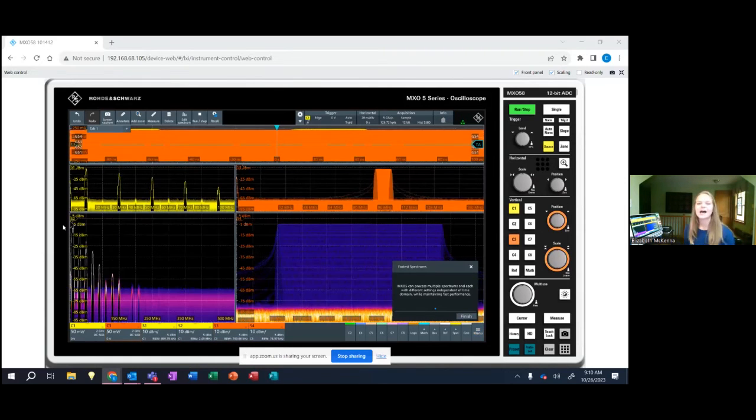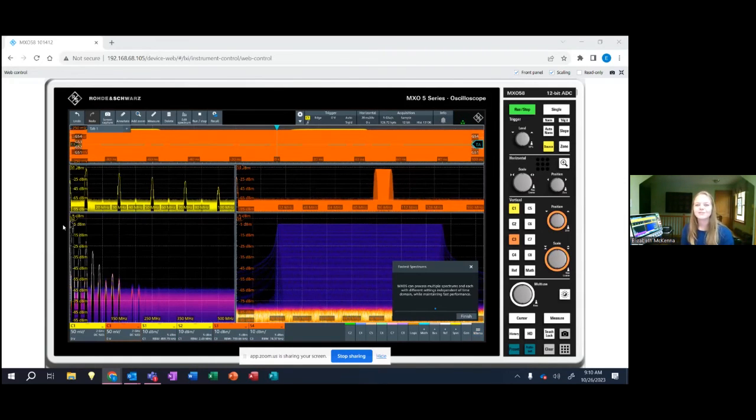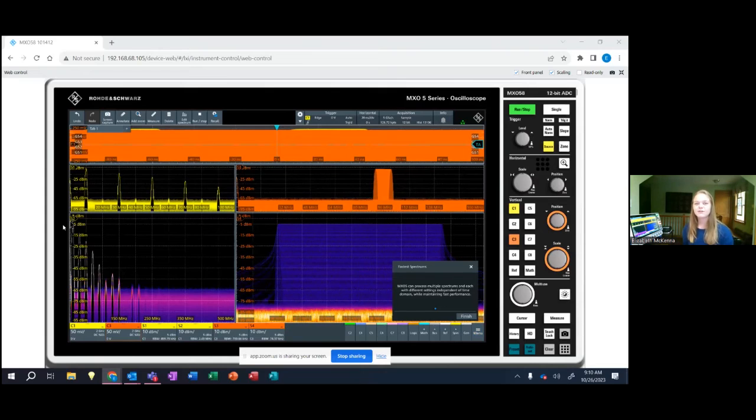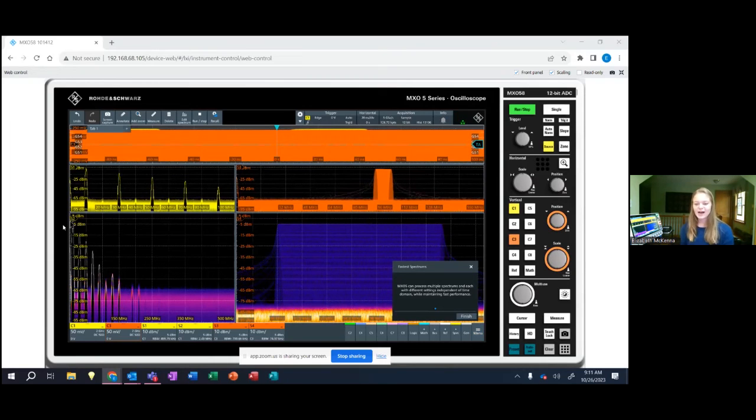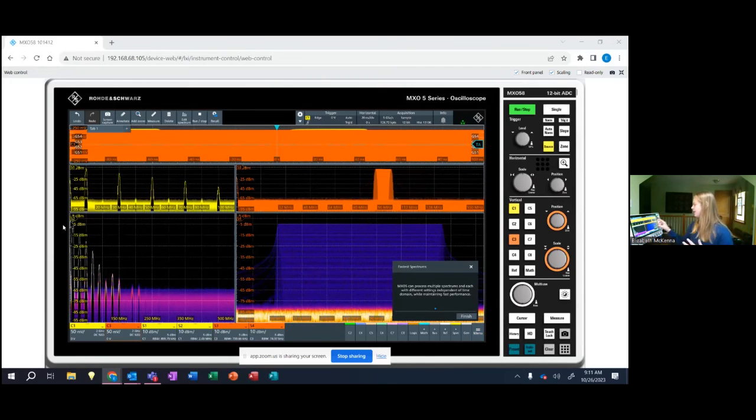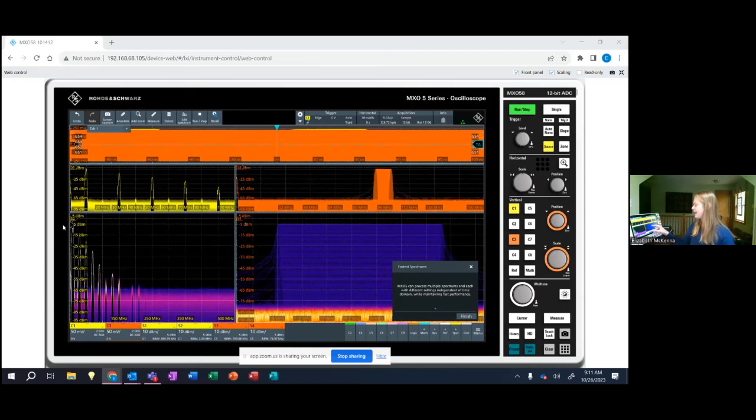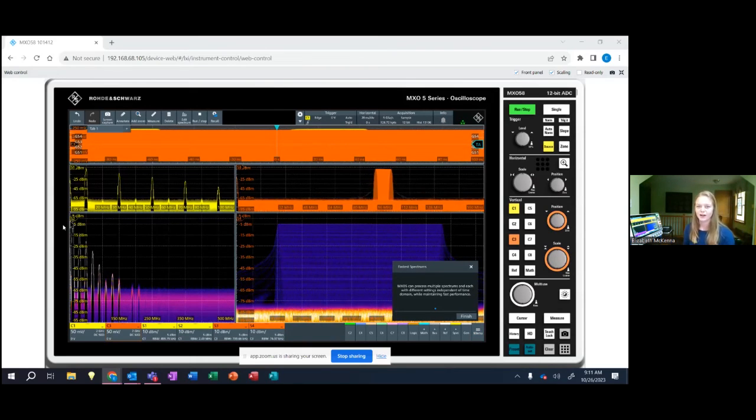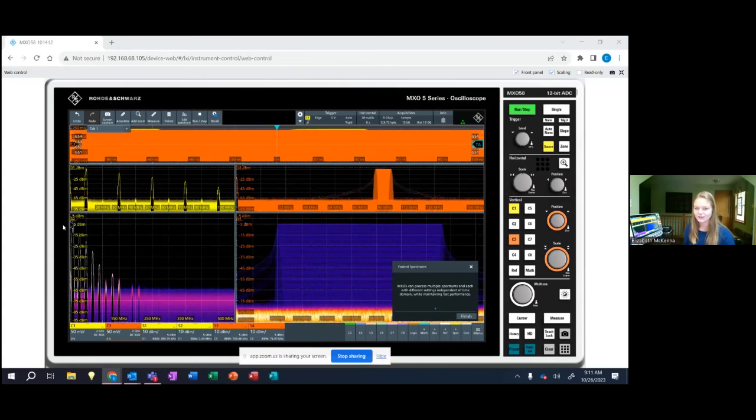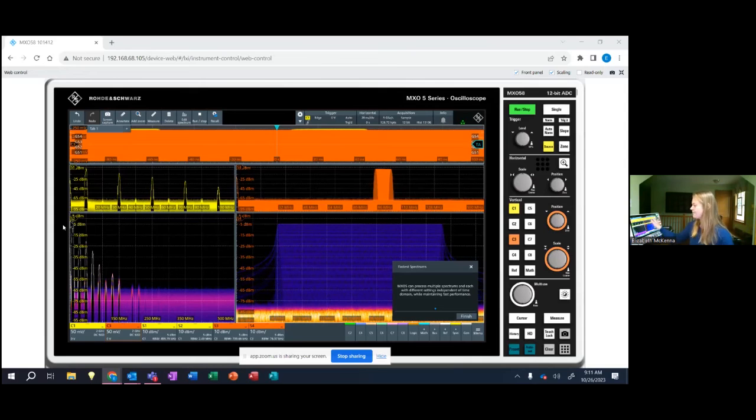So you can see that the MXO5 is processing four spectrums simultaneously and as you can see the update rate on these is really cool. I'm doing a large and a small span on the two different channels right now. So I'm using both of our built-in generators to simulate two different signals and they're shown here up at the top.